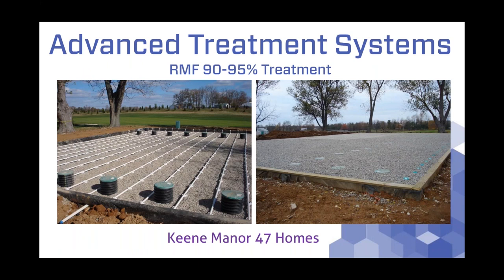Now we're going to take you through the advanced treatment system we installed as a cluster system in central Kentucky on 47 homes. Septic tanks will do approximately 25 to 50% treatment on a residential application. Recirculating media filters — which is what we're going to talk about today — like a lot of advanced treatment systems, will treat the effluent to 90 to 95% efficiency. So primary treatment from septic tanks gives 25 to 50%, while advanced treatment systems that are properly installed, designed, and maintained give 90 to 95% treatment efficiency.